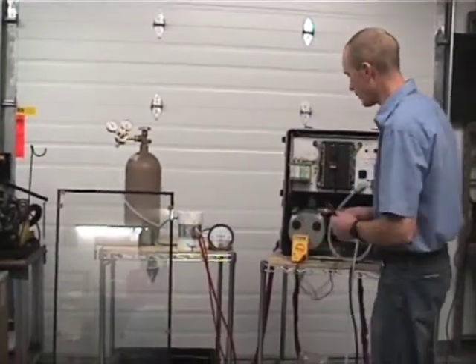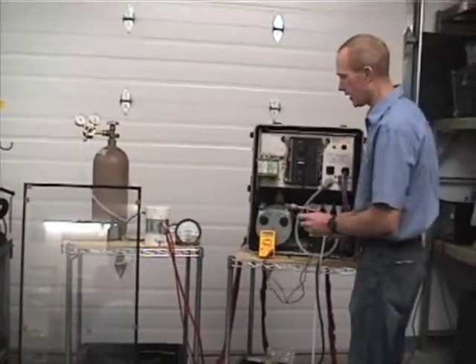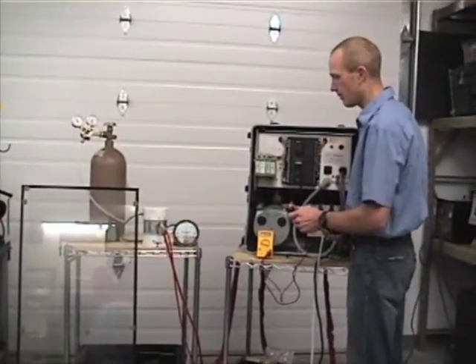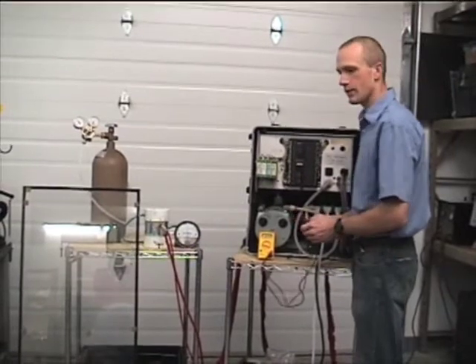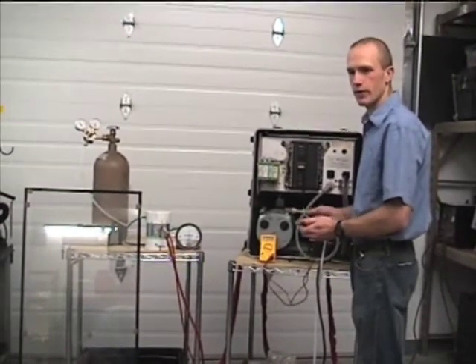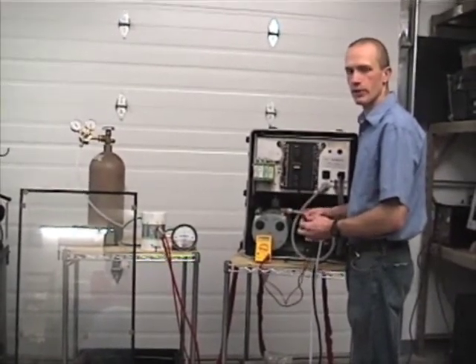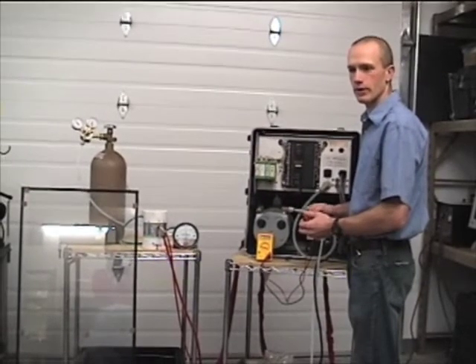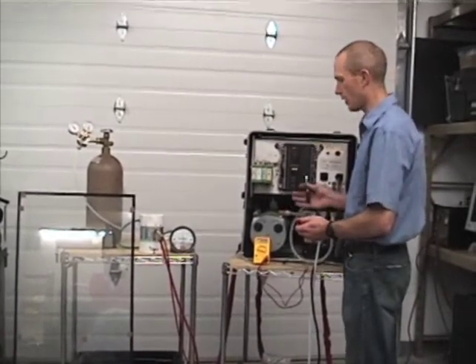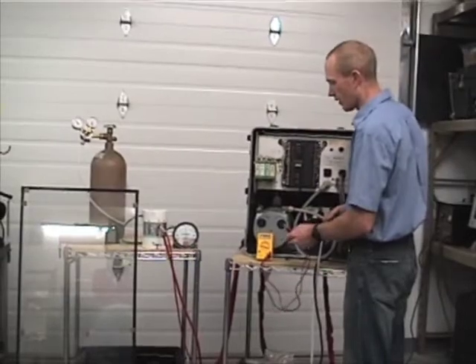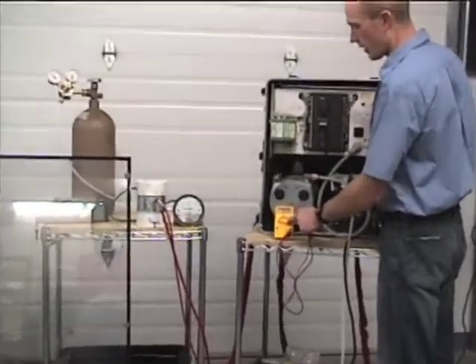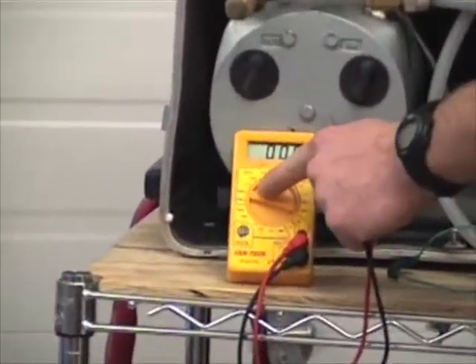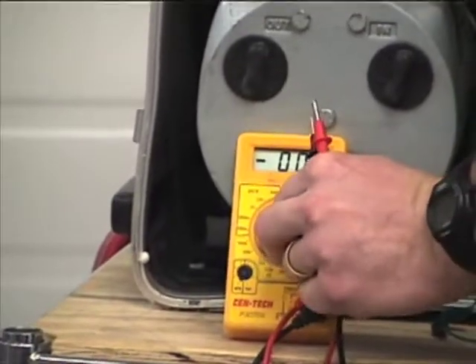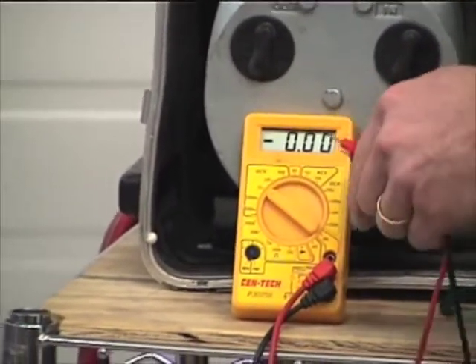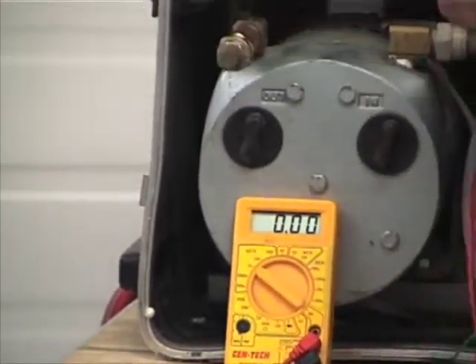The next voltage measurement that we're going to take is with the machine seeing 100% argon. The first setting, the zero setting, was no argon present, and now we want to tell the machine what 100% argon looks like. So now on my voltmeter again, I'm still on DC volts, but I'm going to change the range to 20, and that just puts it on a different scale.